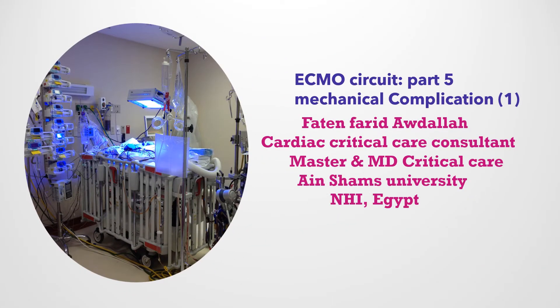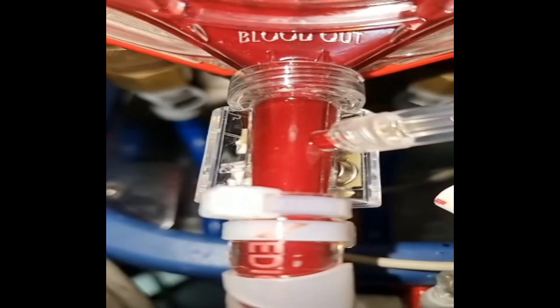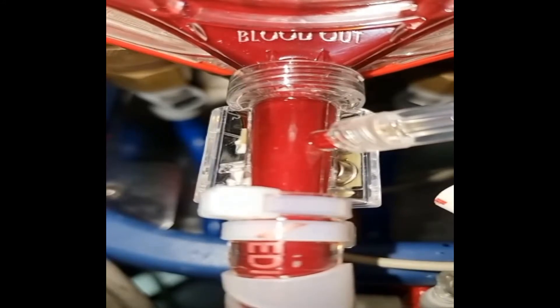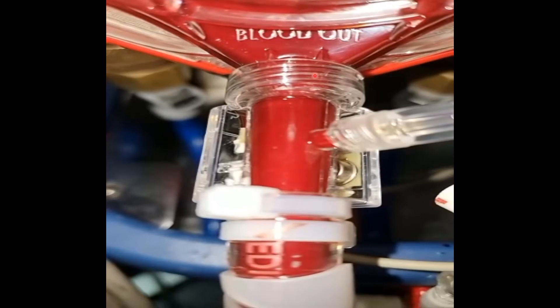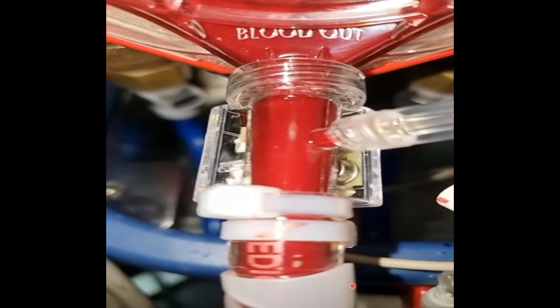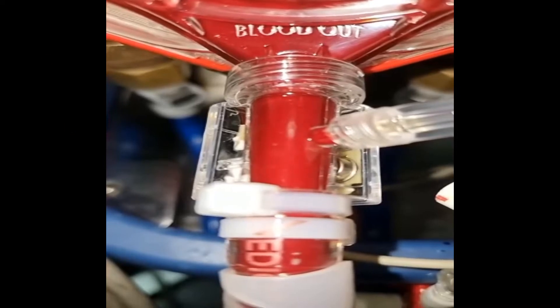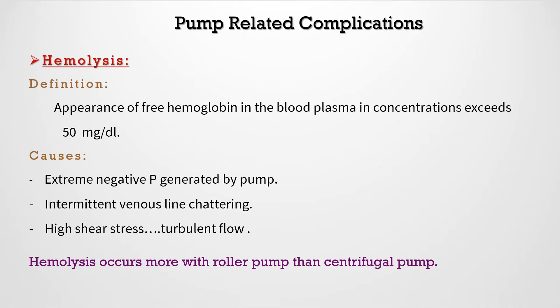ECMO circuit complications. In this lecture I will cover complications of the circuit itself, the machine, and its components. I will divide the complications into two parts. The ECMO circuit is a closed circuit that starts and ends at the patient, with continuous flow and no pulse, unlike the original heart. Every part of the circuit — the cannula, pump, oxygenator, console, and heat exchanger — will have its own complications.